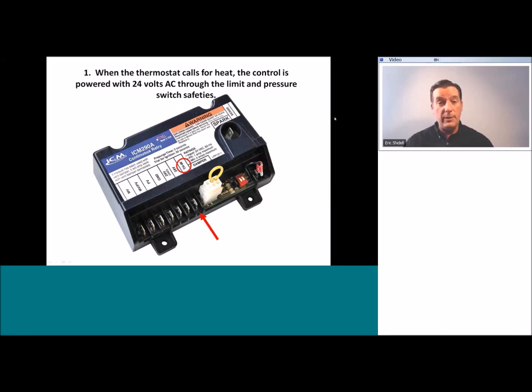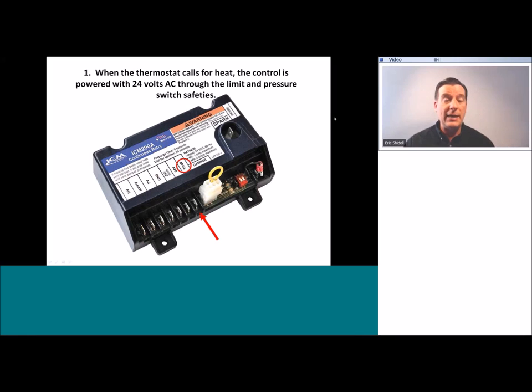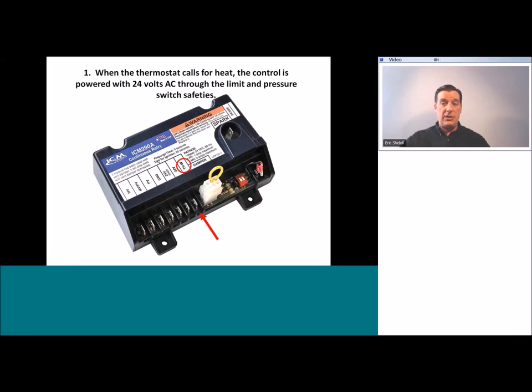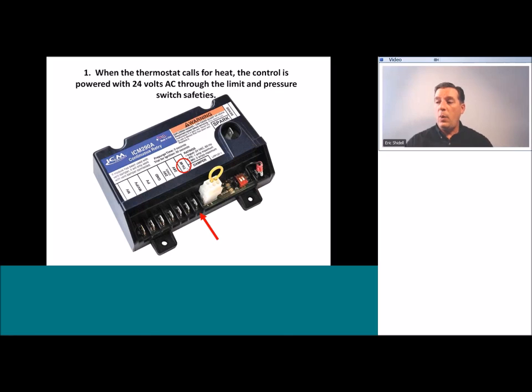The first thing you need to know about all intermittent pilot controls — and all circuit boards in general — is they do nothing until they are powered up, and they are powered up by 24 volts AC. This controller does nothing at all until there is a demand for heat, coming from the thermostat through the limit switches and pressure switch safeties, ending up at the TH connection. TH is short for thermostat. When we receive 24 volts on the TH terminal, the control wakes up and begins its sequence.